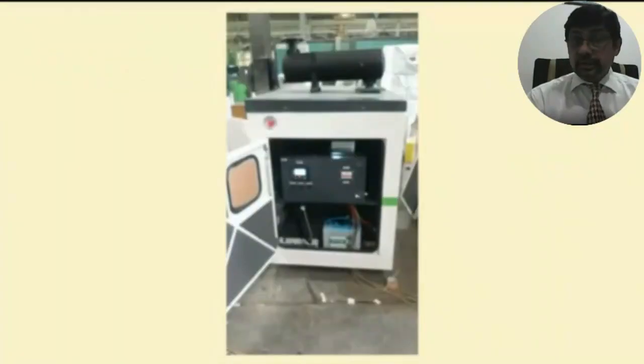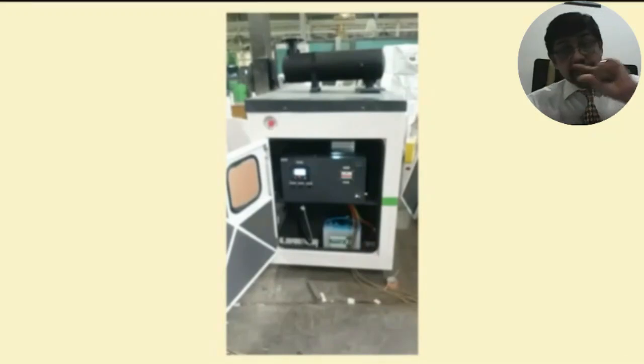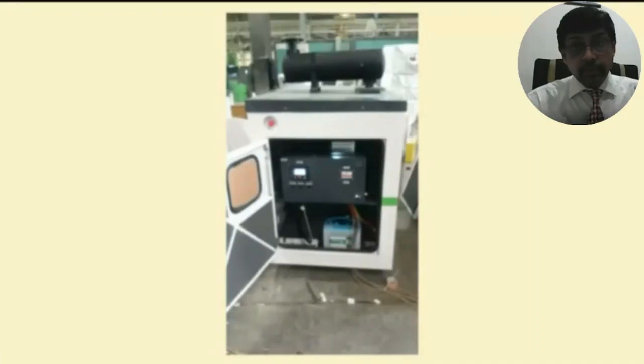Yeah, next. This is the control panel of the engine, which monitors the engine. The control panel which we just discussed some time back was the DG set, that is the diesel generator control panel. The diesel generator control panel is basically a panel which takes care of the amperage at which the generator is running, the load at which the generator is running, what is the line voltage of the generator, or the power factor of the generator. How is the power factor controlled? The generator has a power factor of 0.8. It is designed to run on 0.8 power factor.